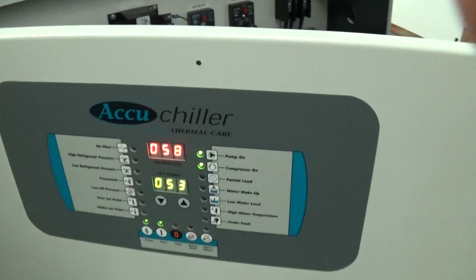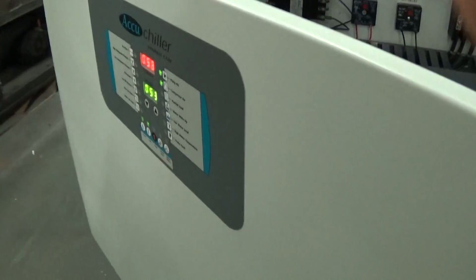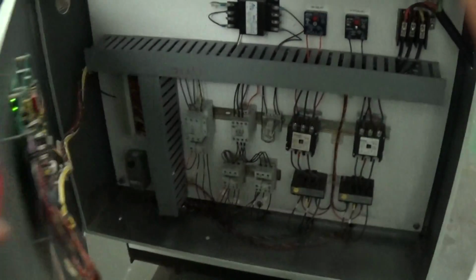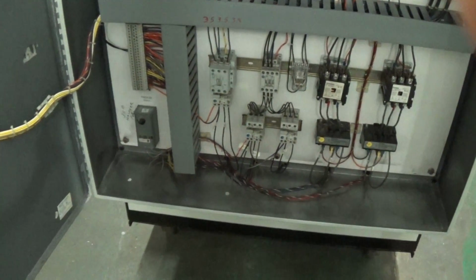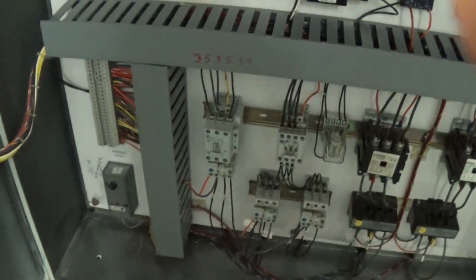So when you first put power to the unit, it is phase dependent. So this contactor and overload here, which we will label, that's for your pump. And when you first put power to the unit, have somebody with this door open over here, looking at the back of the pump with a flashlight, okay? And you want the pump to be rotating clockwise when looking from behind.